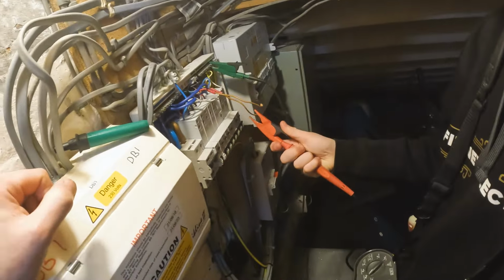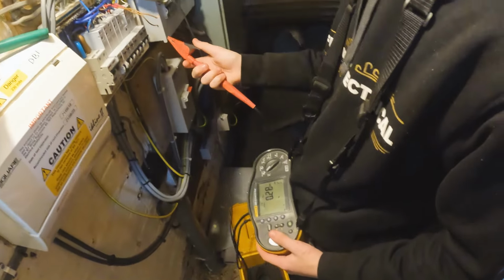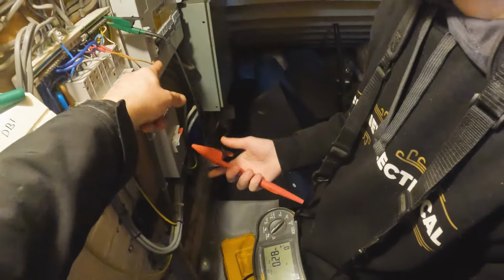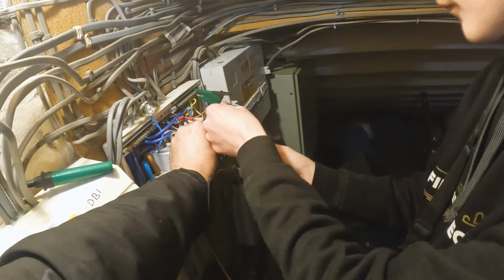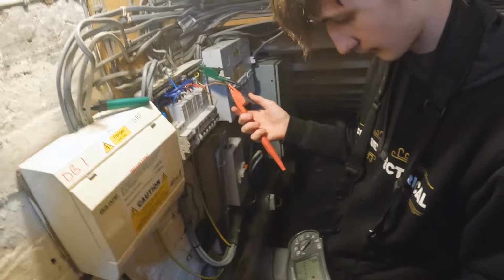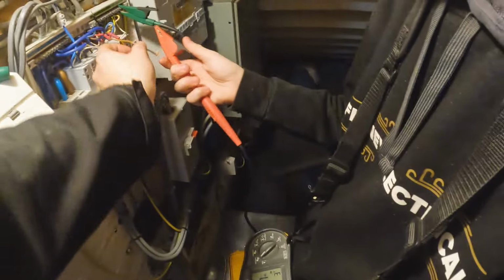So this is on the new conductor, it's a brown. What do we get? Oh, 0.28. So that's quite low. Anything under 1 megohm would indicate an issue, but we need to test them all, don't we? So we'll point that down, we'll send him to hell. I always point that down if it's a bad result, and if it's a good result, I point it up. So here, 0.26, it's bad again. So both lines are bad.